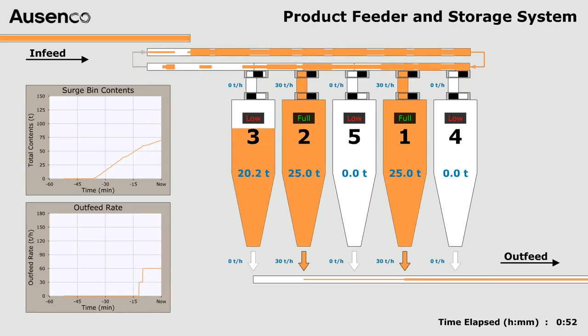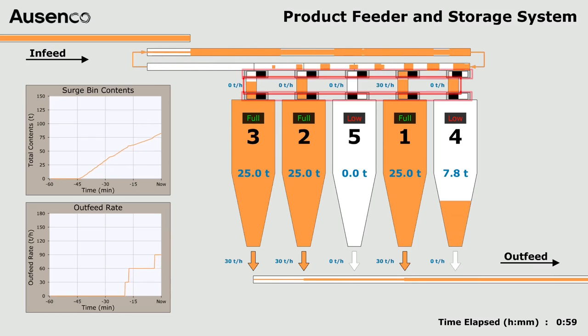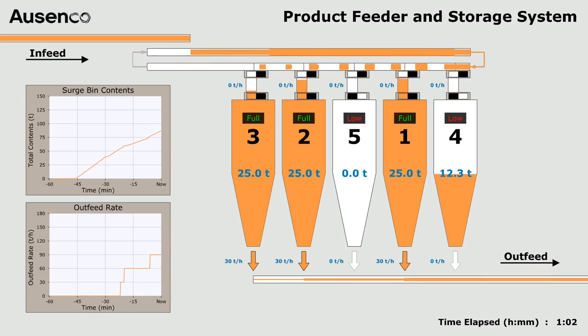Due to fire safety concerns caused by wood dust, flow into each surge bin is controlled by a small hopper equipped with infeed and outfeed gates. These hopper gates control inflow by using small batches until sufficiently high bin inventories minimize further risk of dust generation.